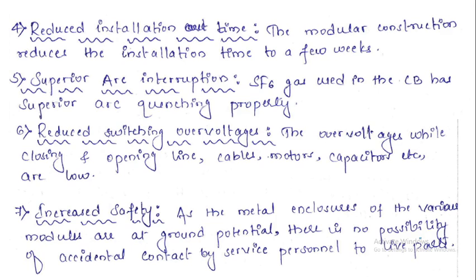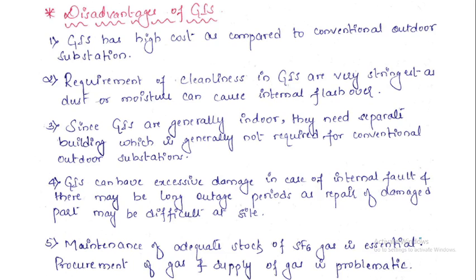Increased safety. As the metal enclosures of the various modules are at ground potential, there is no possibility of accidental contact by service personnel with live parts. All the enclosures of the various modules are directly connected to the ground. So for the person operating GIS systems, the chances of getting shocks or accidents are reduced. Finally, moving on to the disadvantages of the GIS system.